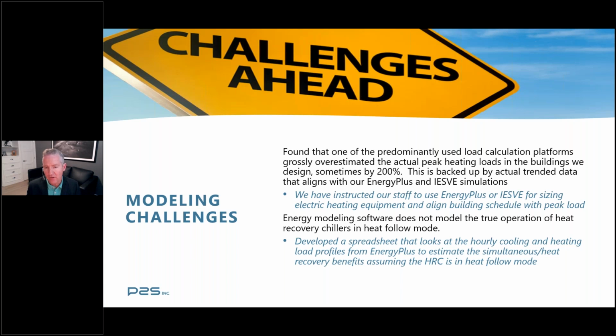We also found that when it comes to modeling challenges on the engineering side, one of the predominantly used load calculation platforms in our industry grossly overestimates the actual peak heating loads in buildings, sometimes by 200% and greater. And this is backed up by us actually getting trended data over years of analysis on the buildings that we designed and operated, and then running our EnergyPlus and IESVE simulations. What we found is EnergyPlus and IESVE more accurately accounted for the sizing we were seeing in the trend data, and our load calculation software, while not a big deal when you're doing gas boilers because it's not a big expense, is a huge deal when you're doing all electric solutions where the cost is much greater. So we've basically decided we're not using that platform.